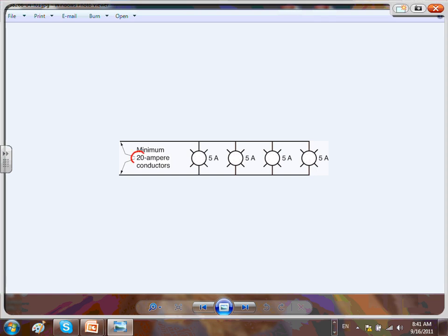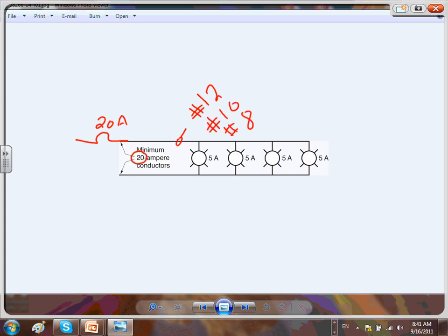This circuit is a 20 amp circuit. Why? Because the overcurrent device here is a 20 amp, so this makes it a 20 amp circuit, regardless of the conductor size. This conductor has to be at least number 12, but I can go all the way to number 10 or number 8 for voltage drop, and the circuit is still a 20 amp circuit.